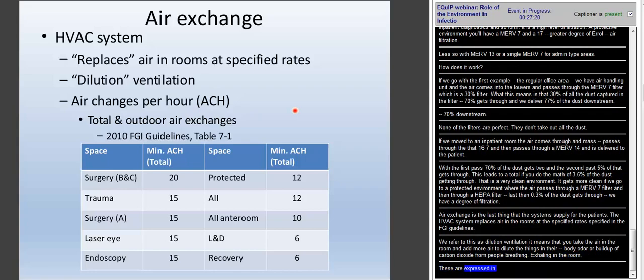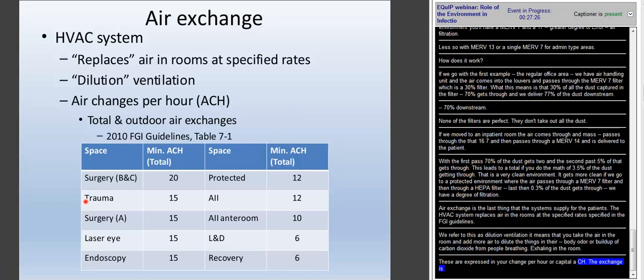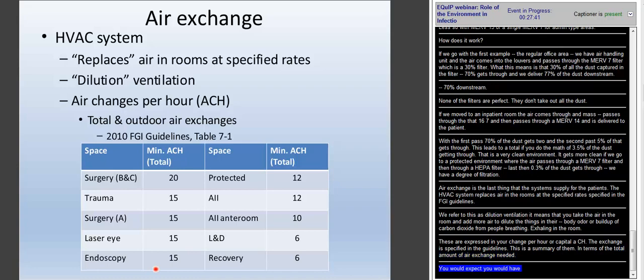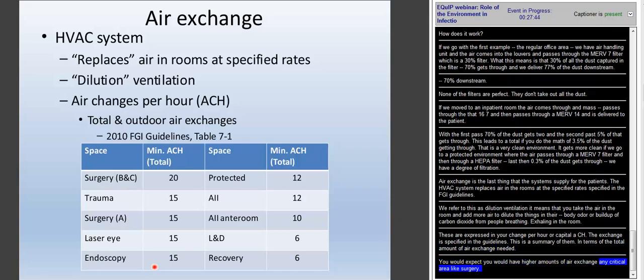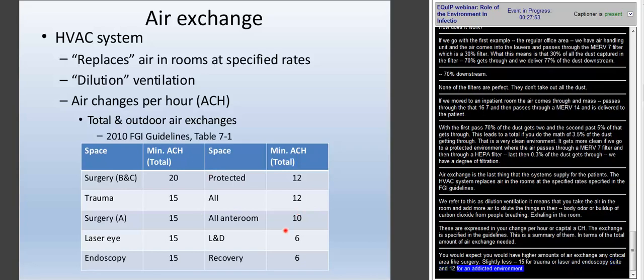And there are total and outdoor air exchanges specified in the FGI guidelines in Table 7-1, but this is a summary of them in terms of the total amount of air exchanges you need. And you would expect that you would have higher amounts of air exchange in a critical area like a surgery area for B and C surgeries, slightly less so at 15 for trauma, A surgeries, laser endoscopy suites, 12 for a protected environment, 12 for an airborne infection isolation room, 10 for the anteroom for the airborne infection isolation room, and then down to 6 for labor, delivery, recovery, and office spaces. But these are all specified in the guidelines.